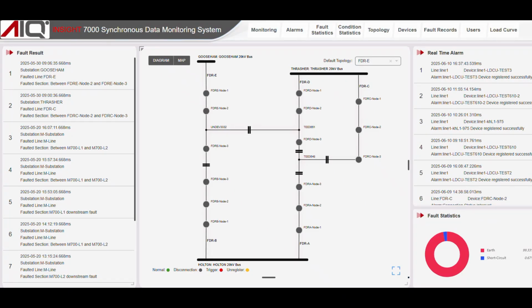This is the home page of the master station software. The column on the left is a list of fault records showing the date and time of occurrence of fault, the substation, the faulted feeder, and the faulted section. On the right is a list of alarms from the devices, and at the bottom are fault statistics for the network being monitored. The middle shows a model of a 20 kV network in East Anglia, UK, which we use for the purposes of fault simulation and demonstration.